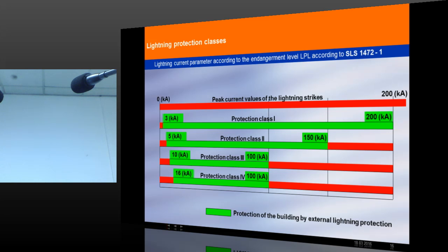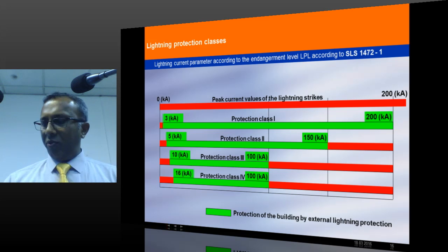Level is nothing but, if you want protection class 1, that means your building is protected from lightning from 3 kiloamperes up to 200 kiloamperes. If you are going for class 4, your building is protected from 16 kiloamperes up to 100 kiloamperes. So this classification is important because when we go for higher and higher current, that means from 100 kiloamperes to 200 kiloamperes, the problem is you need a lot of shielding. You have to create a Faraday cage, eventually a big Faraday cage in your building. You need to have space between your outer wall and your electronic equipment. So all these things will increase the cost. So the standard gives a proper way to find out what approximate protection class is required for you.